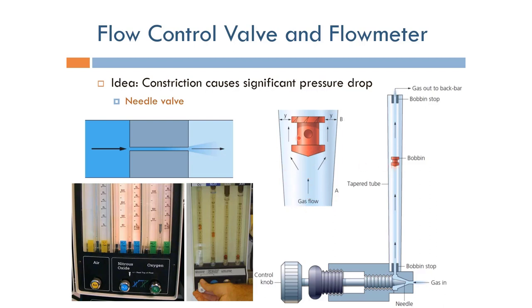Basically, the gas flow will exert a force on this big bobbin, and the bobbin rises to the level that is balanced with the kind of forces that are received from the gas flow.